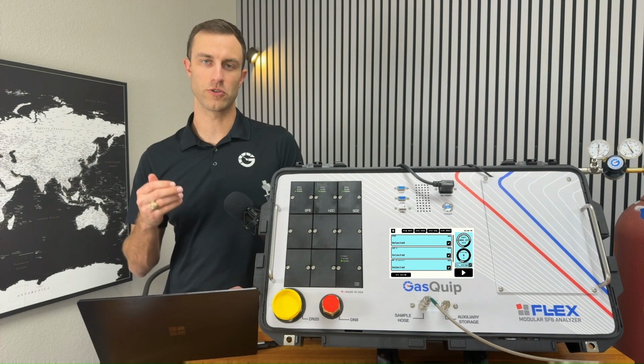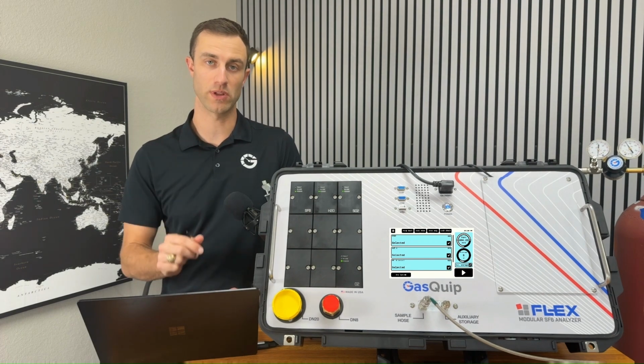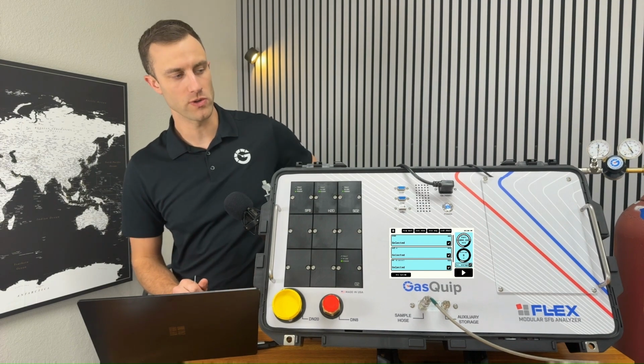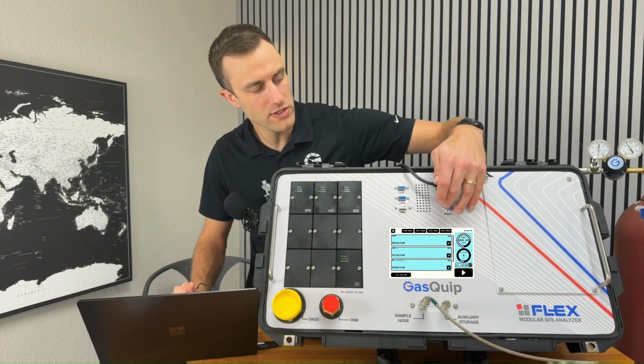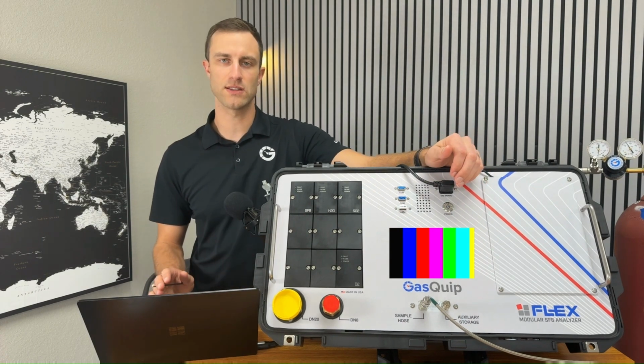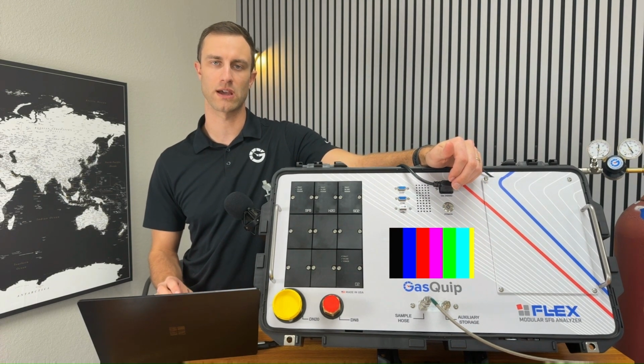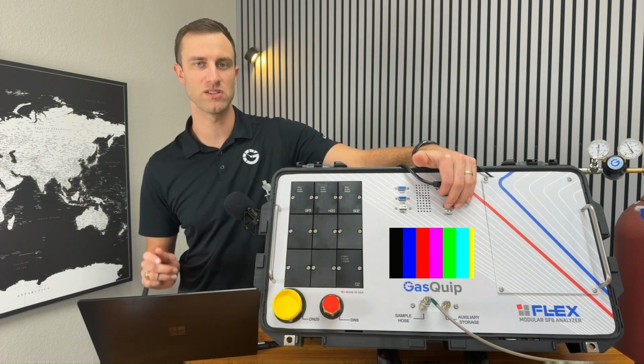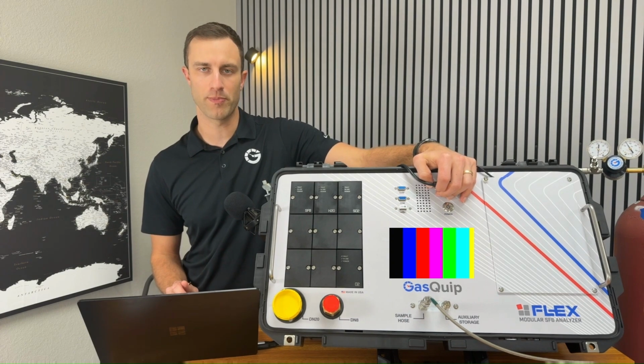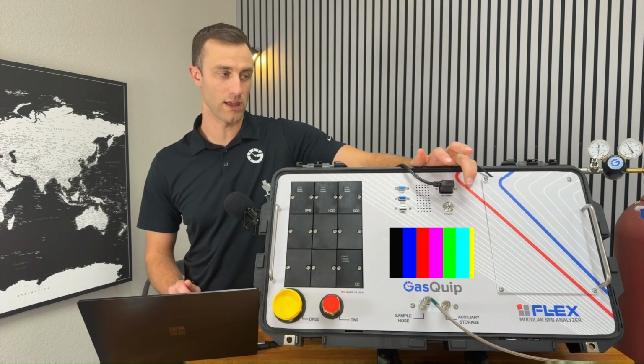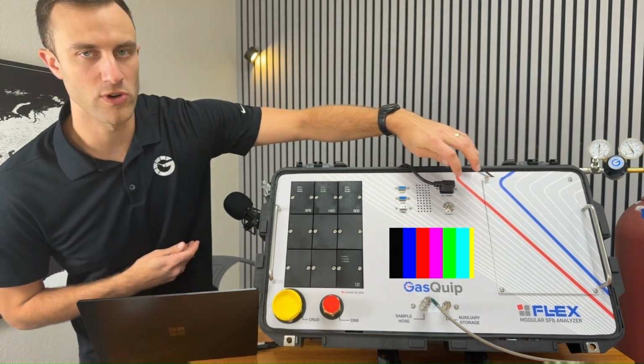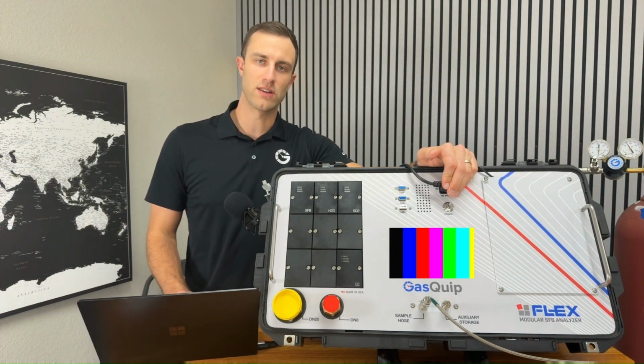If you're having trouble getting your unit powered on and showing a display on the touchscreen interface, the first thing I would do is turn off the power, pressing this power button. Wait about 5 to 10 seconds, let those capacitors inside the power supply regenerate and get some power to them, and then try pressing the power button again to restart the boot sequence on the unit. Always check your actual plug. Make sure it's plugged in all the way at the unit and also the wall. The power source needs to be 120 to 240 VAC if you're going to get that unit on, so anything that is outside that range is not going to be able to power the Flex.